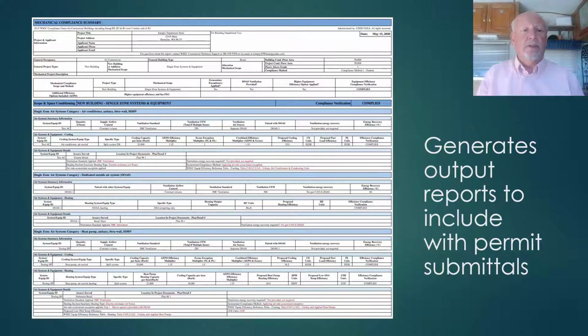Once you've completed that, then you can generate your output summary report. This has all the information required to verify compliance of your equipment with the provisions of the Energy Code. This is what would be submitted to the jurisdiction with your permit submittal. This can be either printed out and turned in at the time of permit, or it can be transmitted electronically.